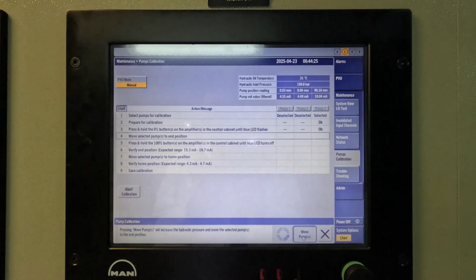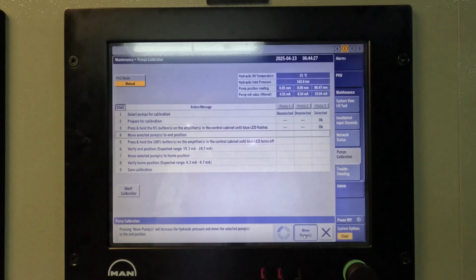The software will move the pump to the end position. You will see the pressure here in the HPS drop down to about 10 bar and then rise up again. Okay, as you see, the pressure has dropped, and now it is rising back up. Rohit, stand by. Let it move to the end position, then we press the 100% button. Can you please ask the second engineer to check for leaks? Second engineer, come in. Yeah, copy. The moment there's no leak. All right, so we have no leaks in the system. Everything is within range. So now let's go to the next one.